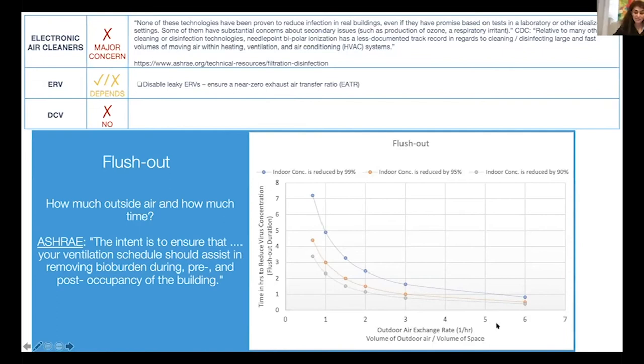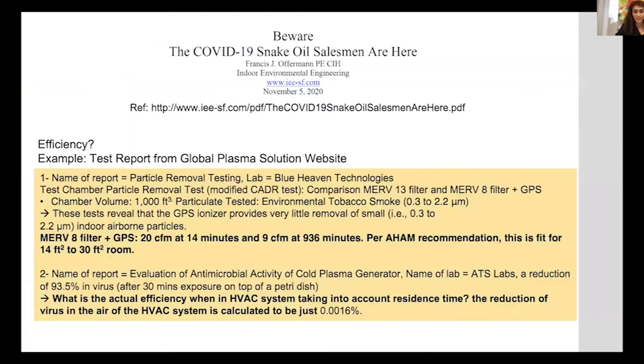And on the x-axis is the air exchange rate. It can be from outdoor air, but also through your filters or through air cleaning. If you follow the orange line, ASHRAE says to reduce your indoor concentration by 95%. So for example, if you have an outdoor air exchange rate of 2, you go up and look at the orange line, and you only need 1.5 hours of flush out. So if your occupants are coming at 8, you can just start your building at 6.5. You can have your minimum outside air and your air going through your filters and that should be enough.